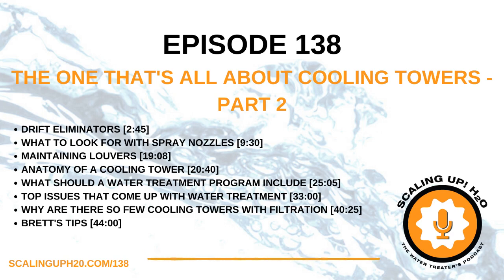Well, Brett, we've talked all over the map when we talk about the anatomy of a cooling tower. Can you help summarize that so we can all visualize it a little bit better? Yeah. So an open cooling tower, right? I explained it last week as a big metal box, but it's got PVC components that make it up. The PVC components we talked about are the air inlet louvers, where the air is introduced into the tower. Then you have the fill media, where the water and the air interact, where the heat transfer takes place. Above that, you have the drift eliminators, whose job is to keep the water droplets inside of the tower. And then you also have the water distribution system, usually a PVC pipe with spray nozzles to spray the entering water over that fill. So those are the general components.